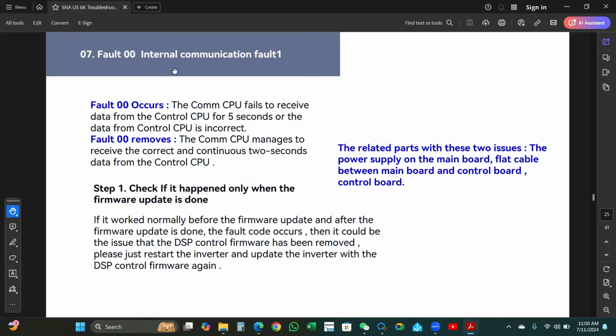Number 7, fault 00, internal communication fault 1. Fault 00 occurs when the COM CPU fails to receive data from the control CPU for 5 seconds, or the data from the control CPU is incorrect. Fault 00 is removed when the COM CPU manages to receive correct and continuous data from the control CPU for 2 seconds. Step 1, check if it happened only after a firmware update. If it worked normally before the firmware update and the fault occurs after the update is done, then the DSP control firmware may have been removed. Please restart the inverter and update it with the DSP control firmware again.